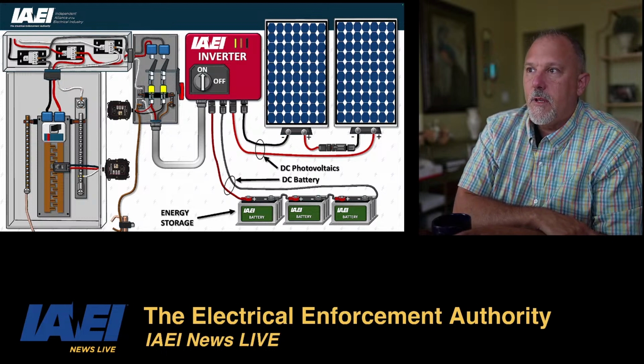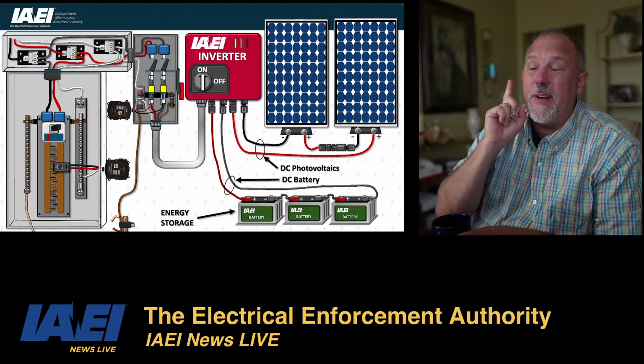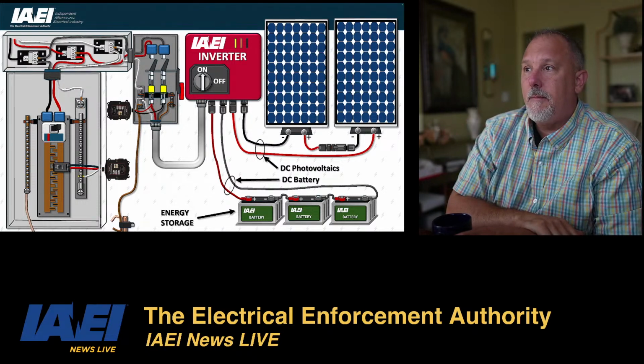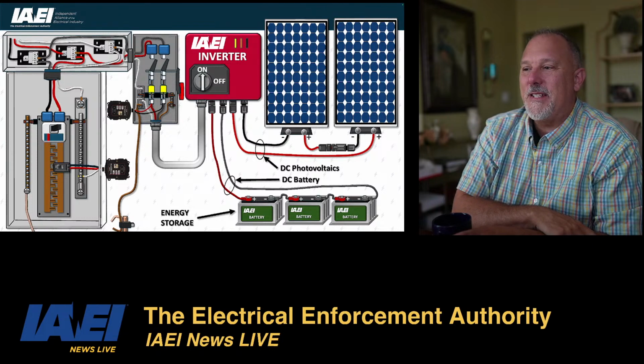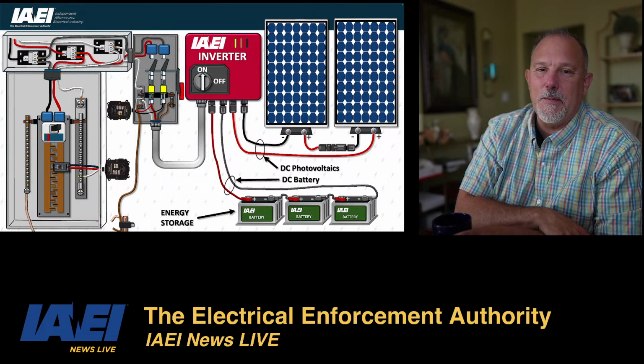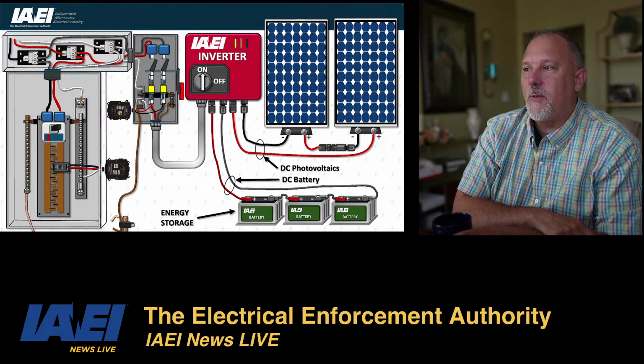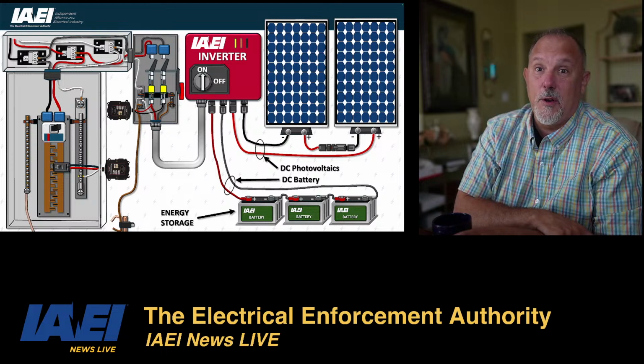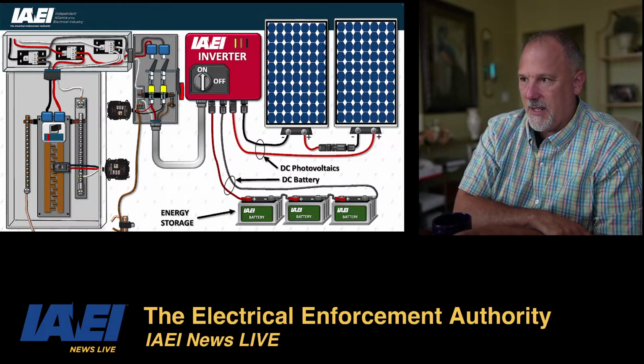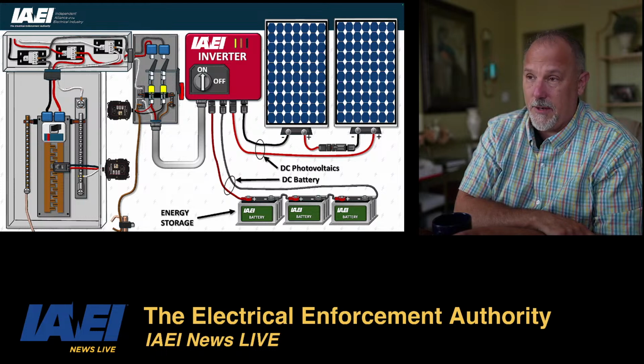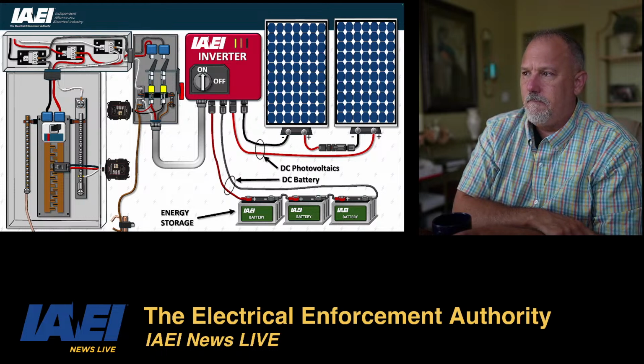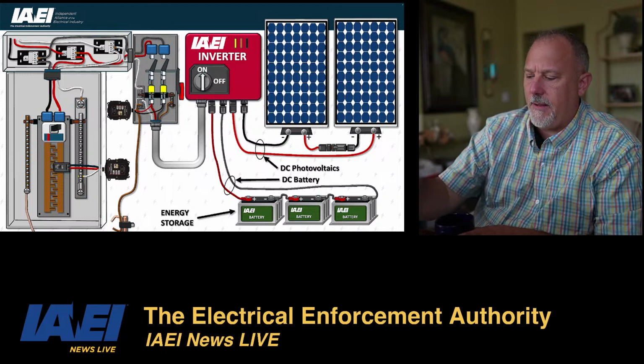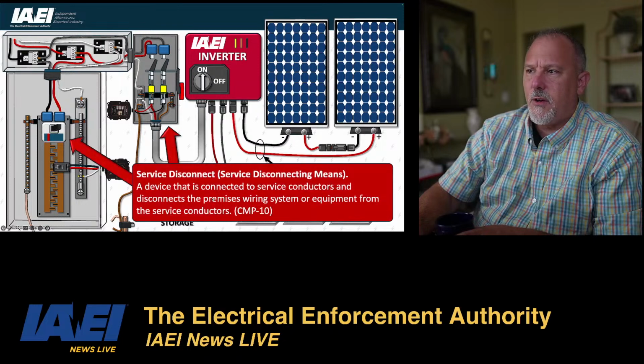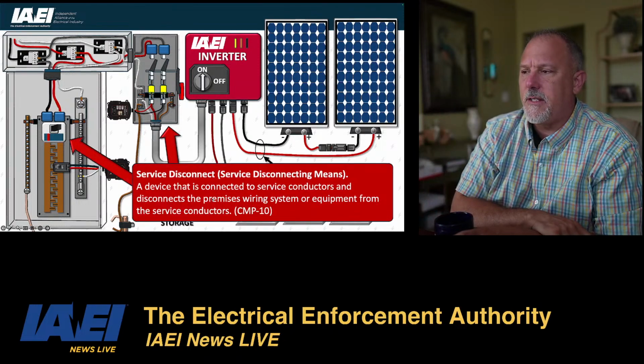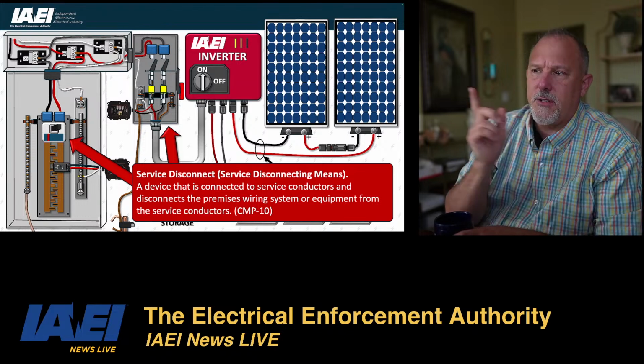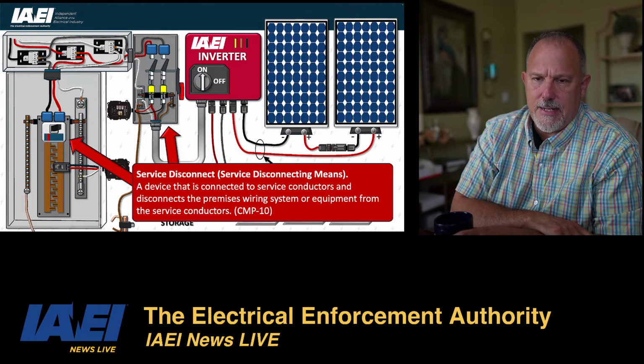Okay, so in this case now, the inverter is not service equipment. The only reason I put the metal raceway, the conduit, in there like that is because I already had the image drawn and it was easy. It doesn't necessarily have to be in a raceway, right? What else do I have in there? I have my line side barriers. Both of those are service disconnects. That's where I'll have to do my grounding and bonding. You'll notice I have surge on the service disconnect, on that disconnect switch.